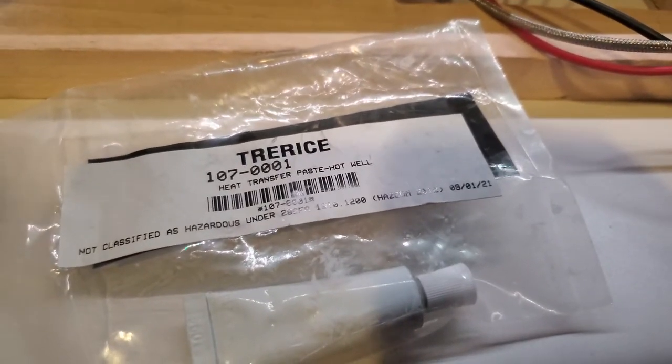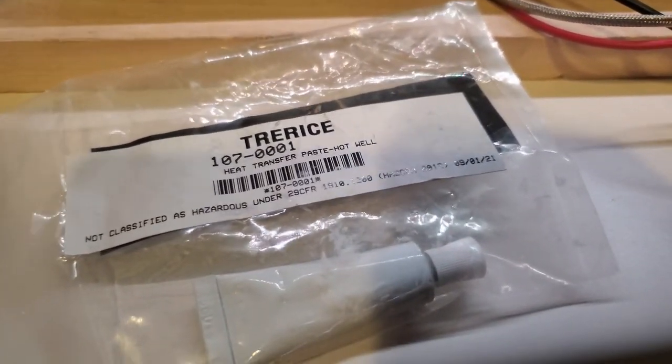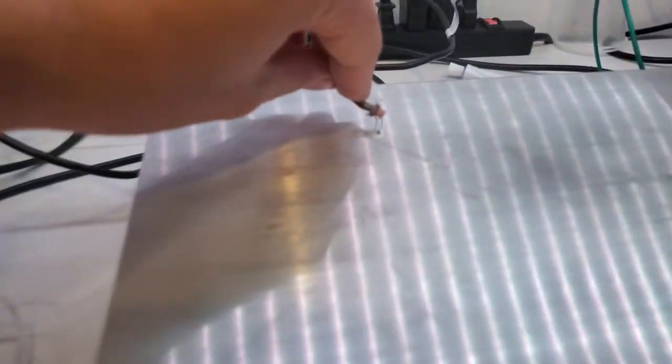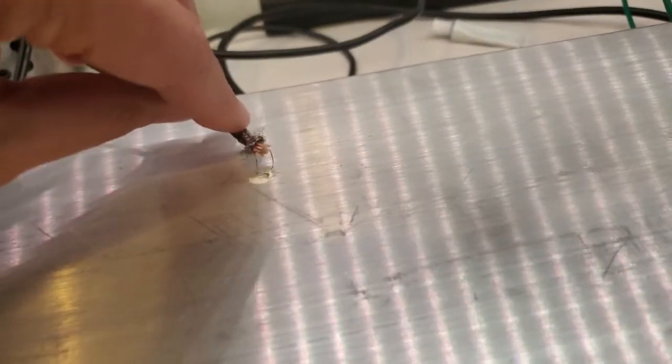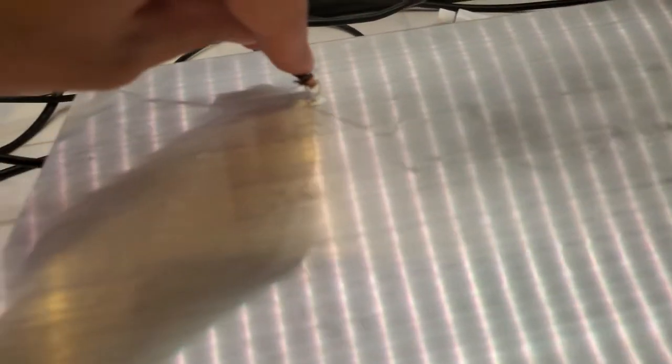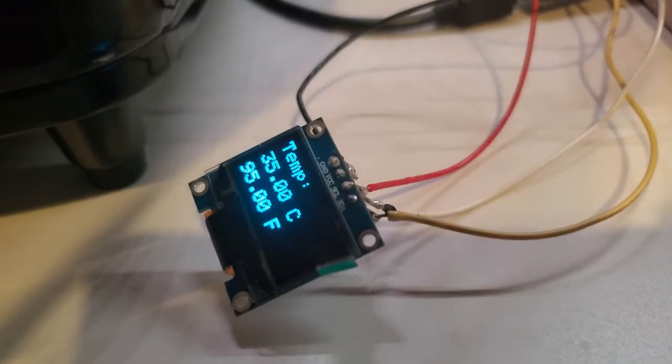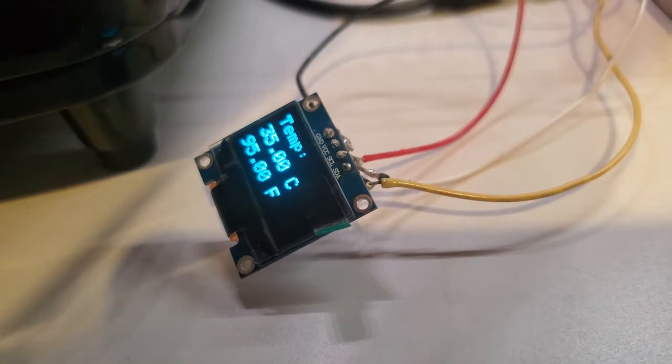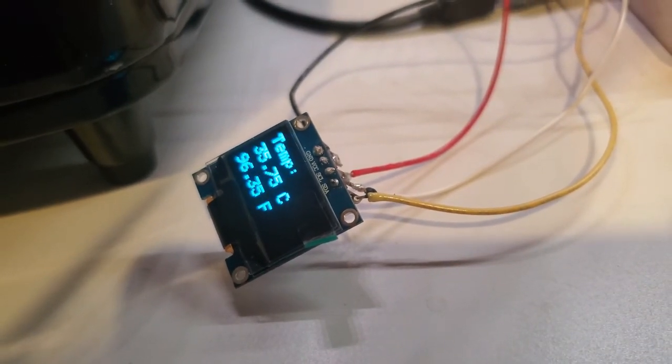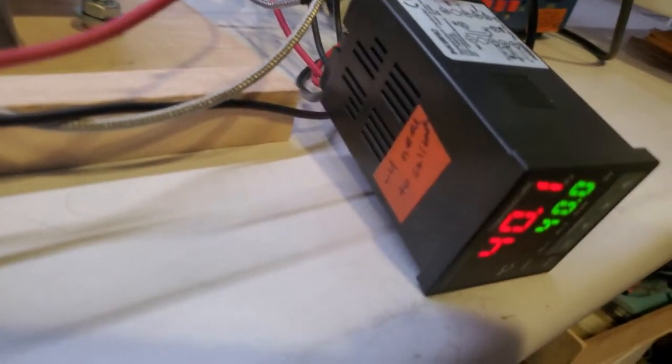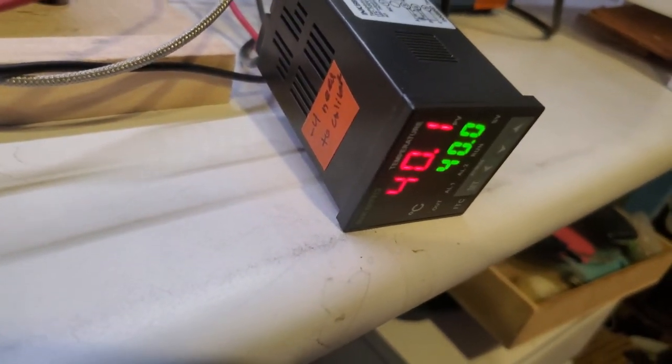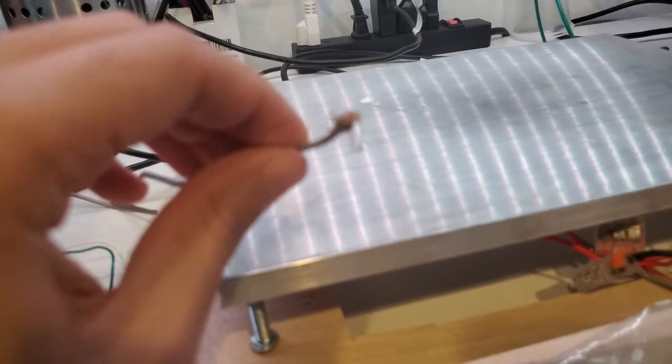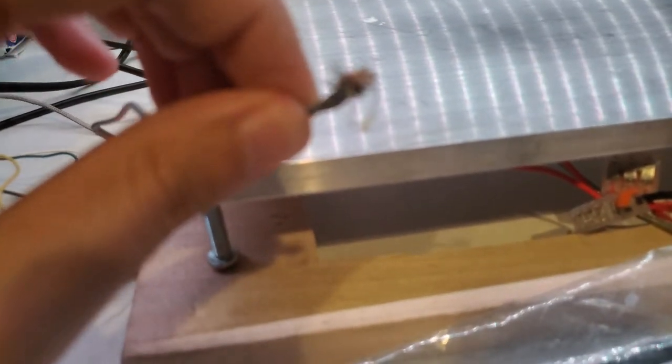What you want to do is take some heat transfer paste—I'm using this Trerice 107-0001, I think I got it from Grainger—and then you just submerge the thermocouple in the thermal paste and make sure it's spread around pretty well there. Kind of push it down and make sure it's in there. Then you'll notice that the temperature is already higher because you've got better heat transfer. So it's reading about 35 to 35.5, and I noted on here that I need to subtract 4 from this temperature module. So this is actually fairly accurate. This should, even though it says 40, it's really about 36, which is about what it was giving me on the temperature sensor reading.